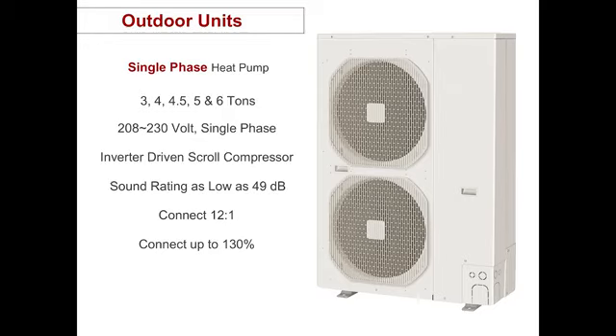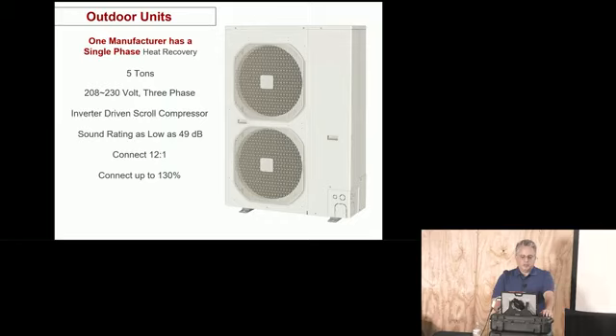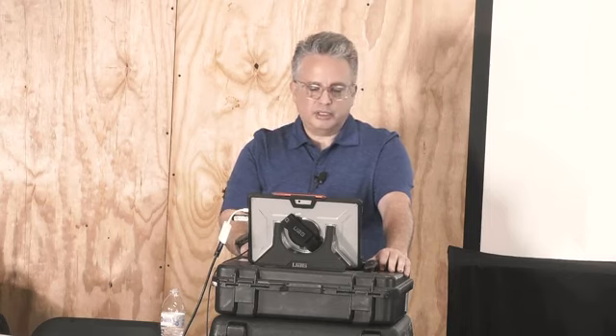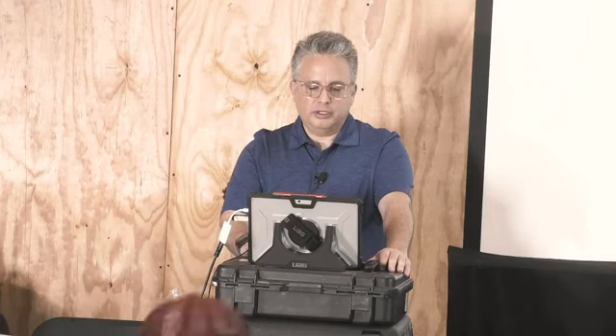introduction, right? Essentials. Single phase heat pumps are available in 3, 4, 4.5, 5, and 6 tons. There's one manufacturer I know is making a 6-ton single phase VRF. So 230 volt single phase typically. I'm sorry? Inverter-driven compressors and 12 to 1. Now there is one manufacturer out there that makes a single phase heat recovery. So now any of you guys working on residential and you want to put in something real fancy that can delight the most demanding of customer, maybe this is your product.